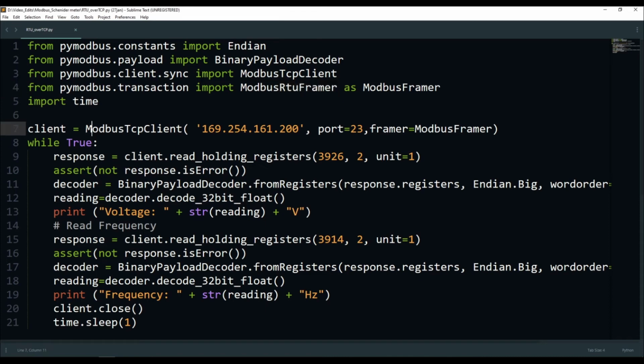Using these two in combination, this line creates an object which will be a TCP client, but internally it will have RTU frames. So you are transmitting RTU frames over a TCP connection, and this is the IP of your RS-485 to Ethernet converter, and this is the port number that you configured in the converter's configuration.